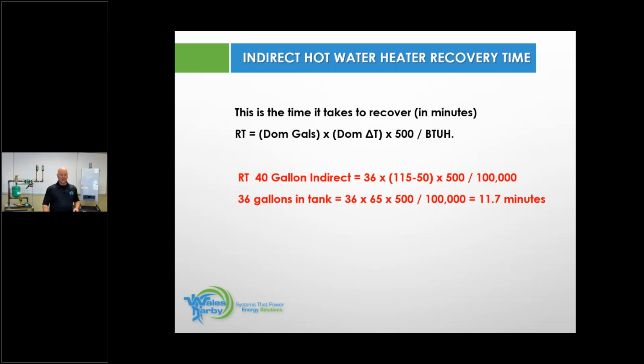And it's always amazing to me when I go to an install, and, we're the NTI guys, let's say an NTI with an NTI indirect, and we helped him lay out the piping. It's his first NTI, let's call it. And he says, holy cow, this thing made hot water in less than 10 minutes. Yeah, that's what it's supposed to do, really. That's no great shakes to us, because we understand the performance. If I pipe it and pump it correctly, that's what it should be: 10 to 12 minutes on most of your standard indirects from a cold start.